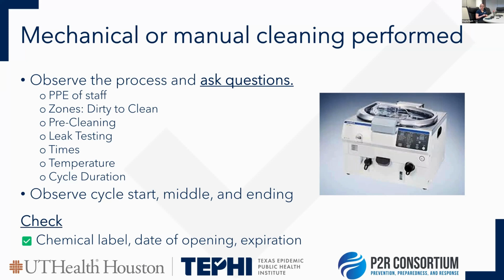If they're doing pre-cleaning, according to the instructions for use, what type of dilution are they using? How do they test their dilution? When were their chemicals open? When do they expire? How do we know that the dilution's correct? Especially if it's one of those devices that is an automatic dilution that it calculates. I know Ecolab and some other companies have automatic dilution sets. Making sure that they are serviced appropriately, they're checked. How do they check it? How often do they check it? And then making sure all the chemical labels you're looking at, making sure that they haven't expired, they're good to use, and that they're okay to use within that specific device.